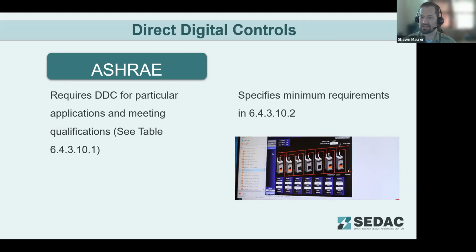But when DDC is required, the system or plant needs to serve at least 3 zones and a fan system brake horsepower of larger than 10 horsepower. For alterations or additions that are adding DDC into those areas, the DDC system does need to cover that new area, or if all the boilers or chillers are replaced, a DDC system needs to be installed if that boiler or chiller replacement is exceeding 300,000 BTUs per hour in capacity. So the system is just essentially laying out if your building's large enough, you need to have DDC controls, and then it lays out the requirements for those control systems.